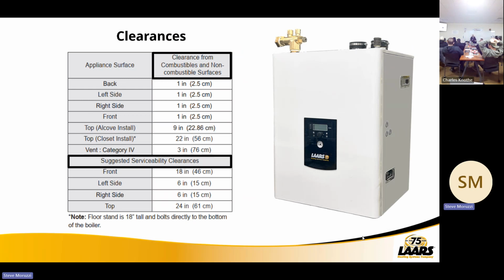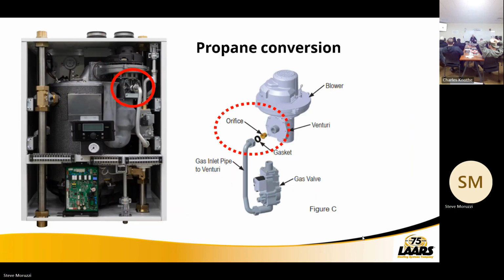Clearance to combustibles, okay, and then suggested service clearances are here as well. Again, very, very simple on the propane conversion, less than 4 minutes. You just take that fitting off, or actually both fittings there, the one off the gas valve, loosen that one, take the one off the venturi, which is where your air and fuel is mixed. Don't forget you have a gasket there. We do give you a gasket kit with each boiler that's mounted inside the cabinet. And by the way, that should stay with the boilers, not go in your truck, okay?